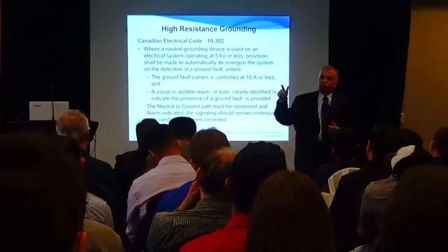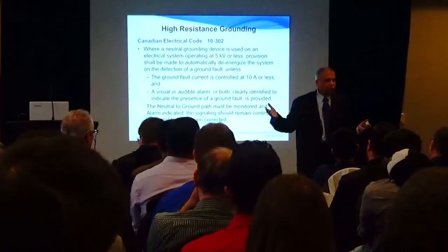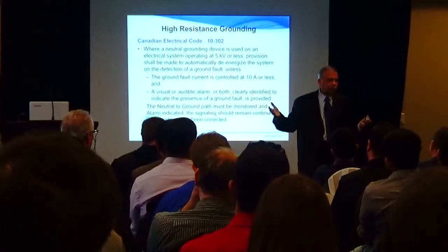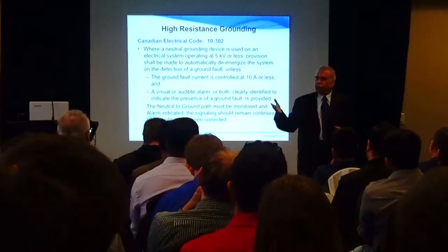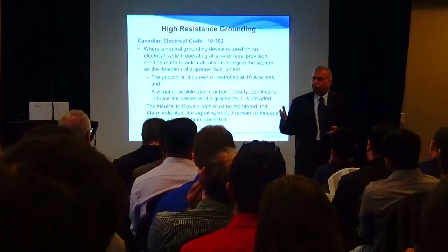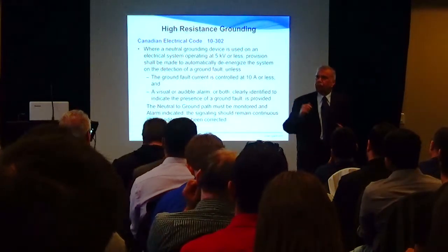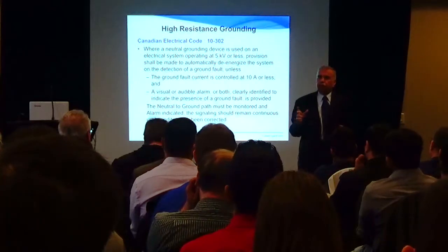When a fault happens, if it is shorted, then you get a good fault current, because your system got converted to a solidly grounded system and you didn't know that. If the resistor is open circuit, the system now becomes ungrounded, you didn't know that, the fault current will not flow and you'll get transient overvoltage causing you multiple failures. So the consequence of resistor failure is not known.